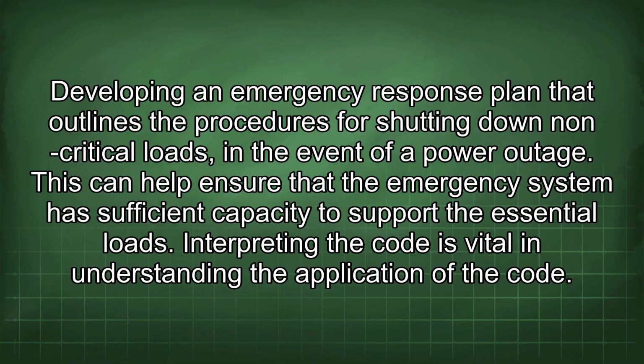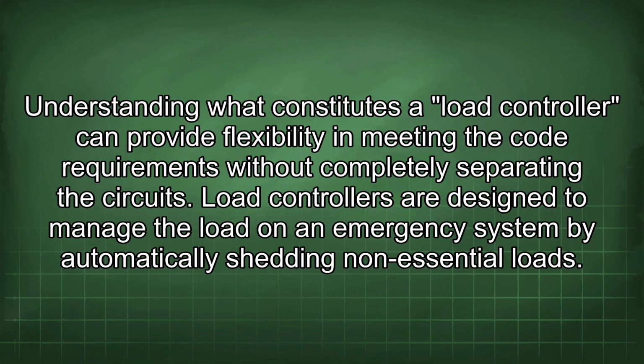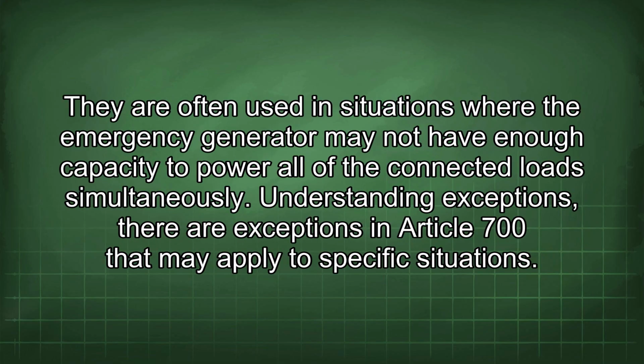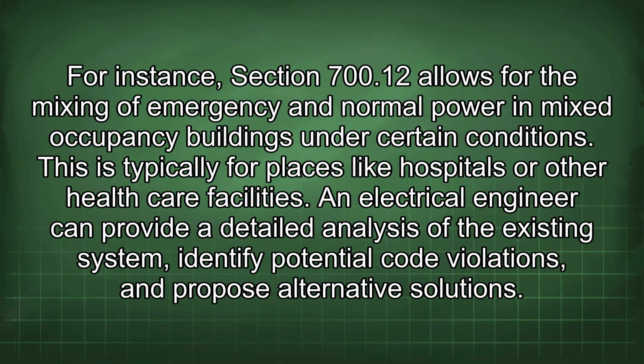Interpreting the code is vital in understanding the application of the code. Understanding what constitutes a load controller can provide flexibility in meeting the code requirements without completely separating the circuits. Load controllers are designed to manage the load on an emergency system by automatically shedding non-essential loads. They are often used in situations where the emergency generator may not have enough capacity to power all of the connected loads simultaneously. Understanding exceptions. There are exceptions in Article 700 that may apply to specific situations. For instance, Section 700.12 allows for the mixing of emergency and normal power in mixed occupancy buildings under certain conditions. This is typically for places like hospitals or other healthcare facilities.